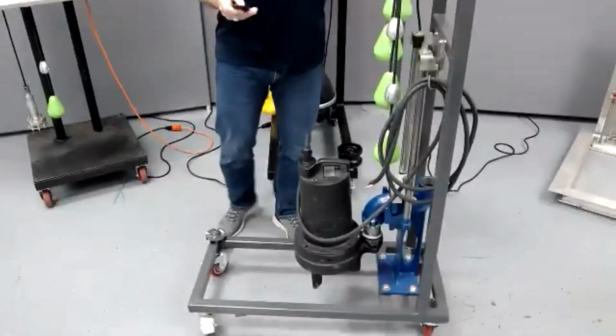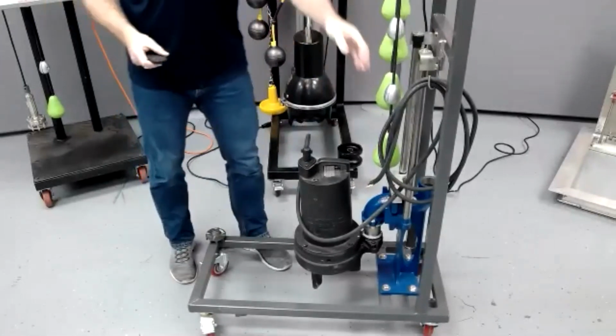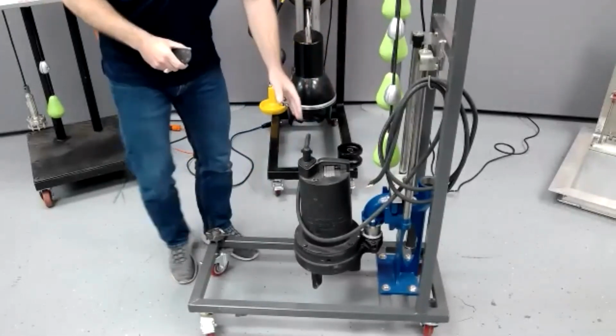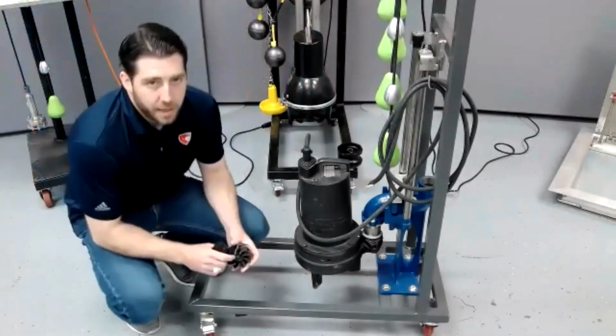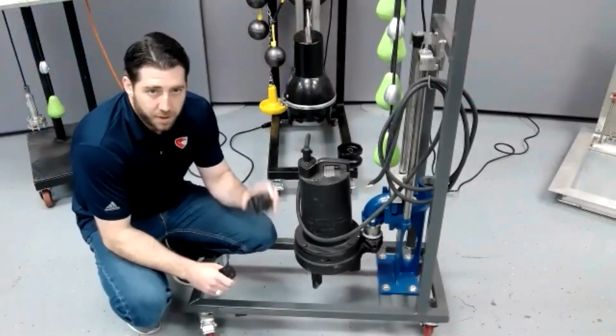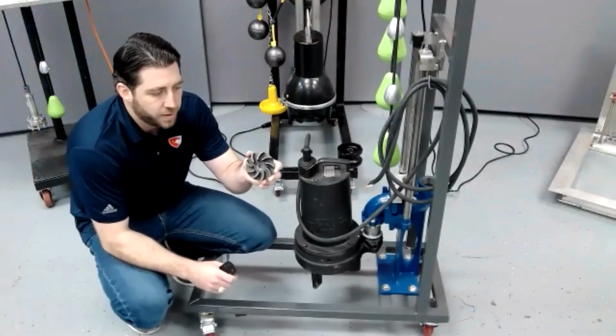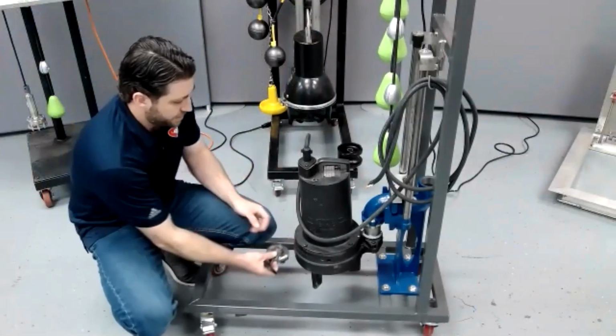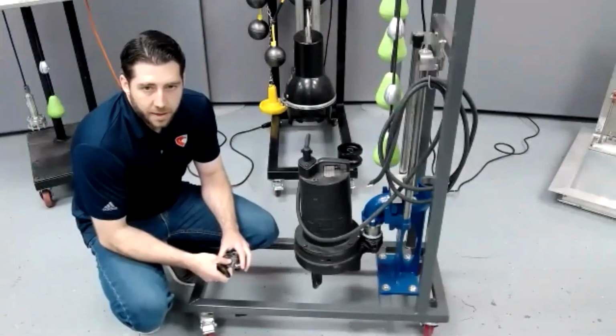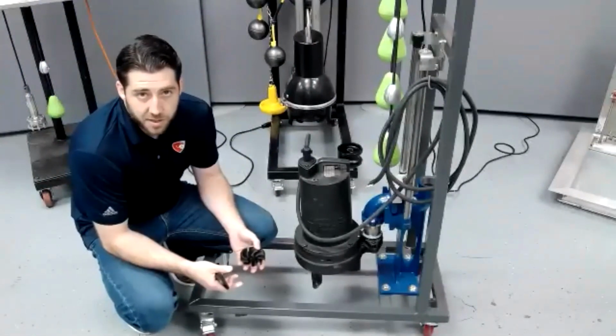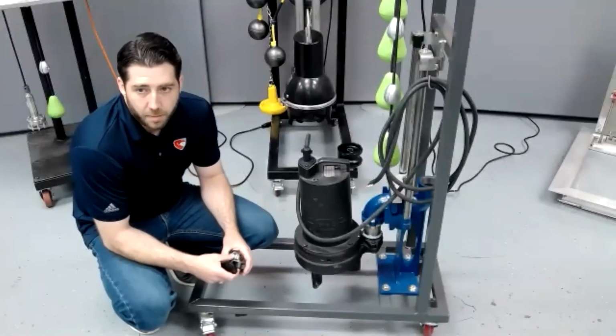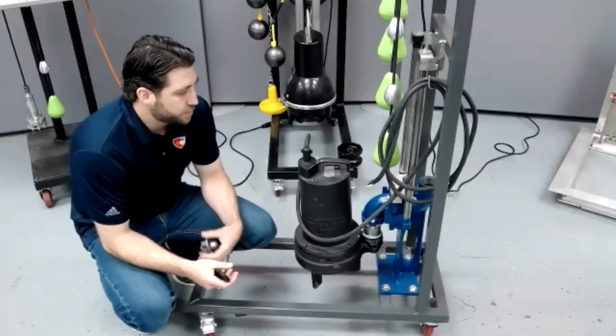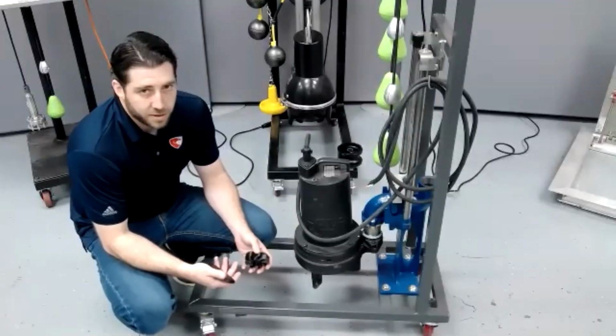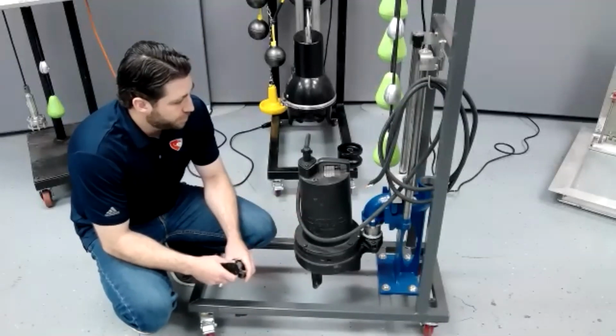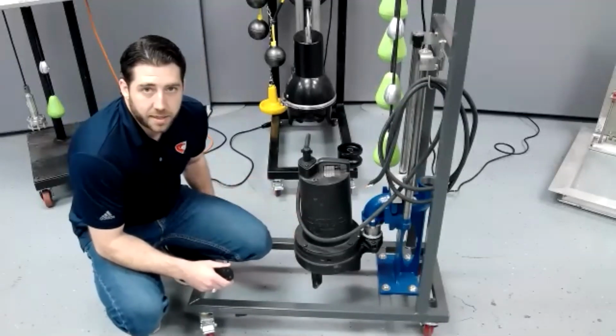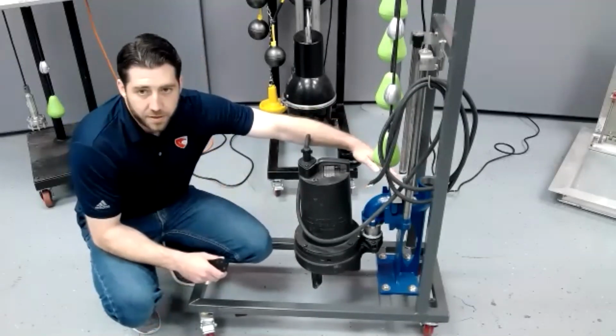So this is the smaller of the pumps that Grundfos offers. This is the Grundfos PIP pump. It's a small non-clog style pump using a vortex style impeller. You can see it's open right there, and that would be sucked up underneath here in the volute. It can pass up to 2-inch solids, up to about 2 horsepower on the sizing on this one. So small storm or sanitary applications, or even large elevator pit applications, is a good place for this type of pump. And when you're using it in a storm or sanitary pit, you could couple it with this removal system.